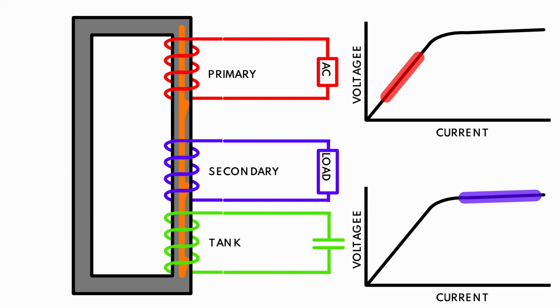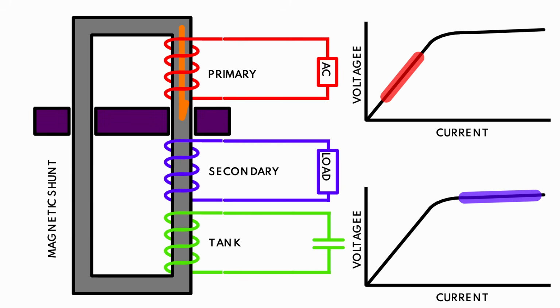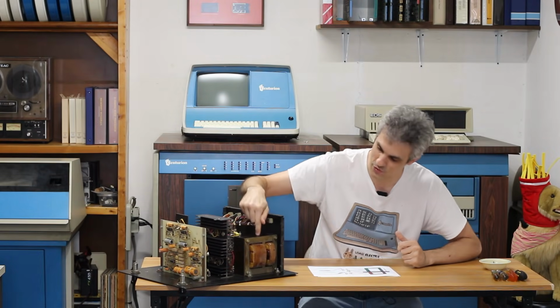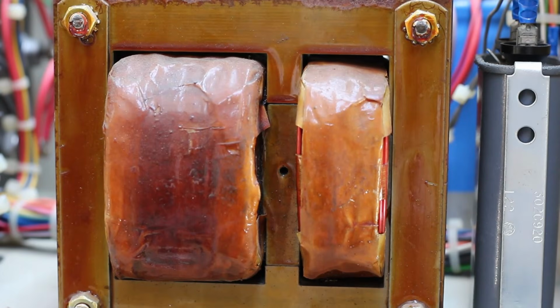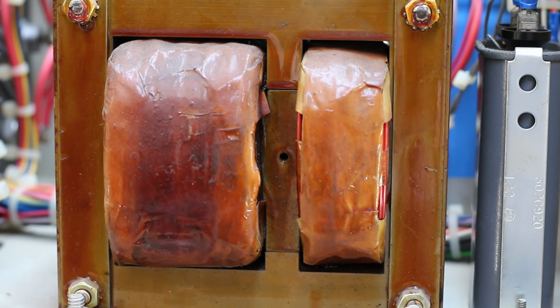Well, that's bad. We don't want the primary to go into saturation. So we want the primary to live in that linear region, and we want the secondary to live in the saturated region. So we separate the two with what's called a magnetic shunt - just this kind of magnetic space that sits in between the two. You can actually see that on this transformer right here, in this open space between the primary and secondary coils.